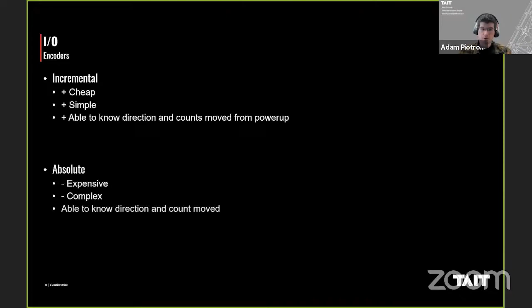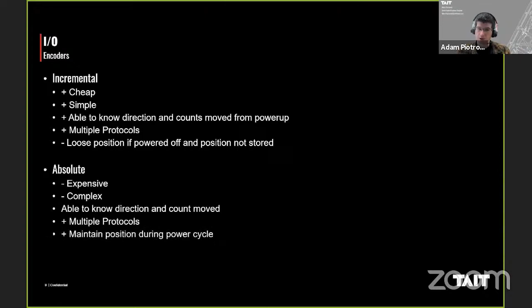You can have multiple protocols for incremental, multiple protocols for absolute. You'll lose position if you're powered down and your position isn't stored, so this is something the control system would have to handle—once it completes a move, it stores that position so that if a power event occurs, you wouldn't have to re-zero or re-reference your axis. An absolute encoder can maintain position during that power cycle.